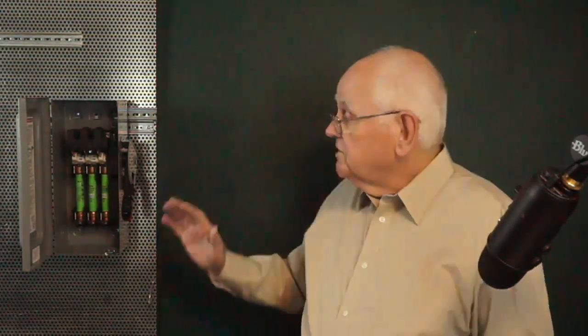And when we operate the handle on the outside, we're operating through a mechanism. We're actually operating the handle on the circuit breaker to open and close it. Now, obviously, this needs to be capable of being locked in the open position so that when we're going to work on the machine, we can do our electrical lockout and tagout, create that electrically safe work condition, right? We've got to simultaneously disconnect all the ungrounded conductors, which, of course, is what the 3-pole switch would do.